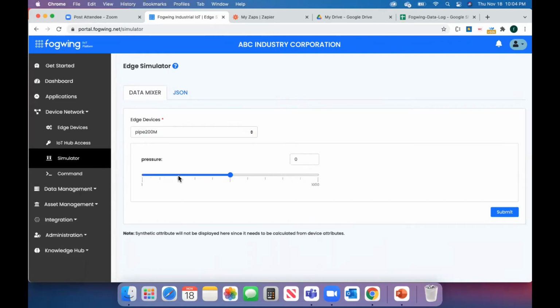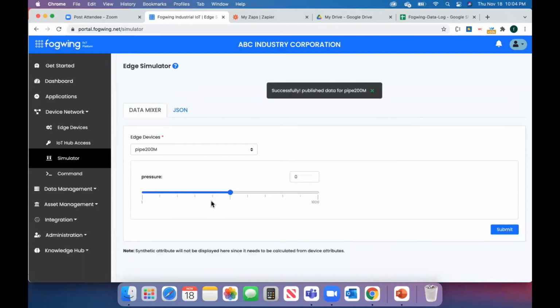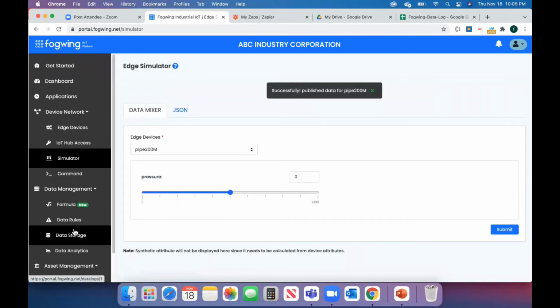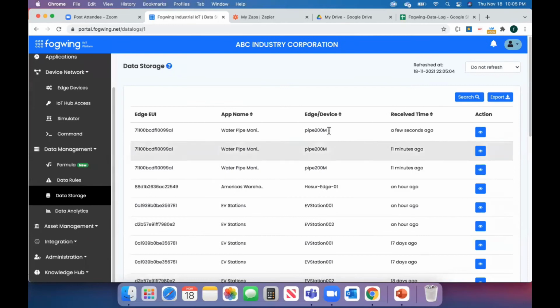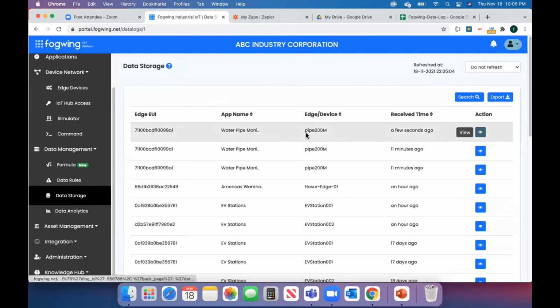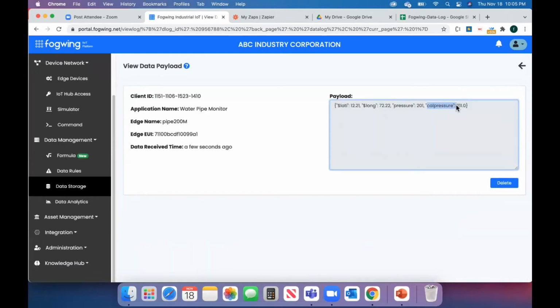So let's take, once again, I'm putting 201 as the value I'm submitting here. Now this has been submitted. Going back to the storage, I should see the new values coming here. Now if you go here, you can see the calibrated pressure. So we are sending the pressure data coming from the sensor, but the calibrated pressure data is 211. So your basic data will also be there, and your calibrated data will also be there.